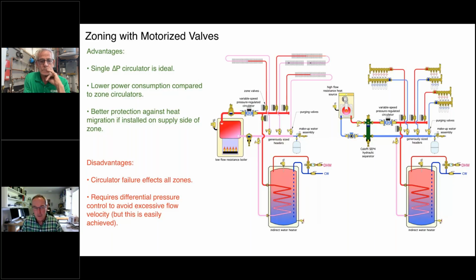I'm sure many of you have probably taken your hand and kept feeling back away from the heat source. Why is this pipe warm? This zone hasn't been on for hours. It's because of heat migration. Some of it is due to conduction along the pipe, but a zone valve on the supply side, fully closed, is a good means to prevent that.